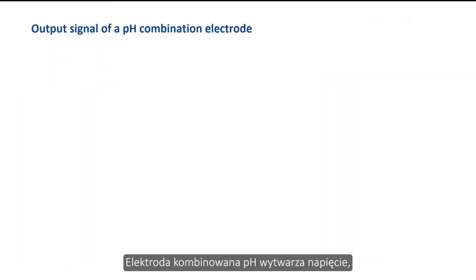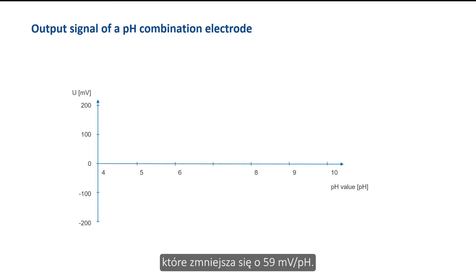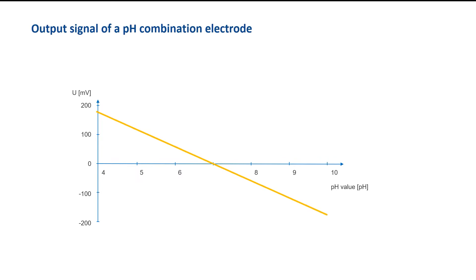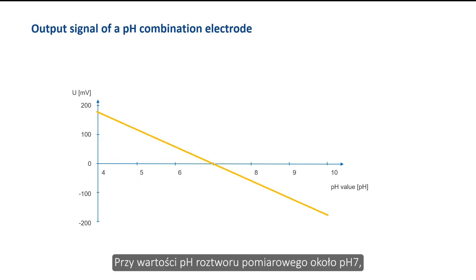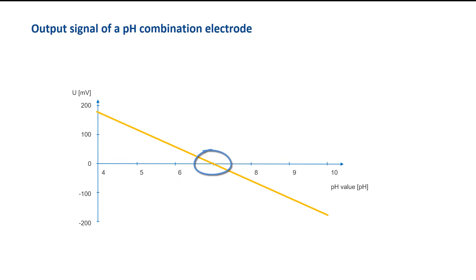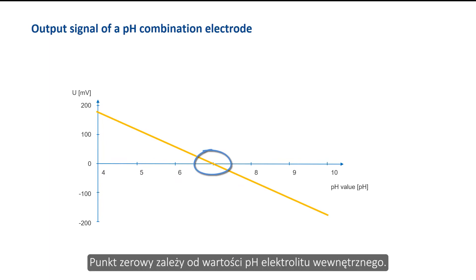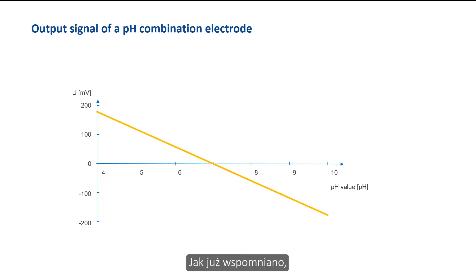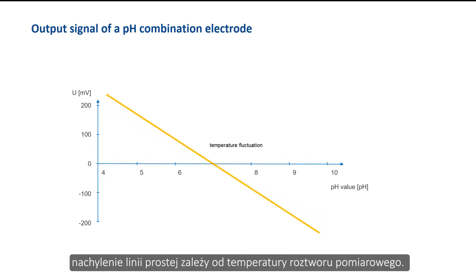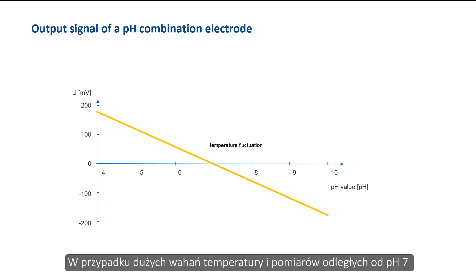The pH combination electrode outputs a voltage which decreases by 59 mV per pH unit. At a pH value of approximately 7, the electrode outputs 0 mV. The zero point depends on the pH value of the inner electrolyte. The slope of the straight line depends on the temperature of the measuring solution. In case of large temperature fluctuations and measurements far from pH 7, temperature compensation may be required.